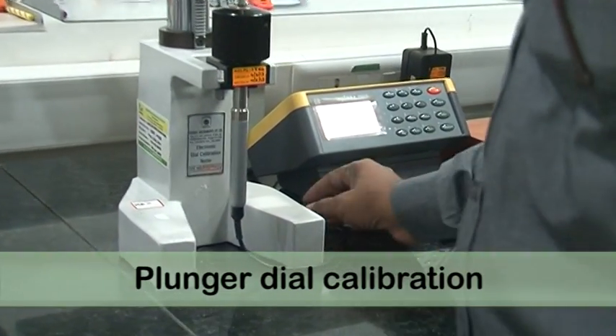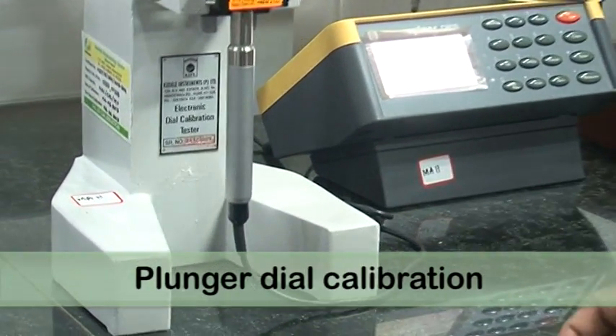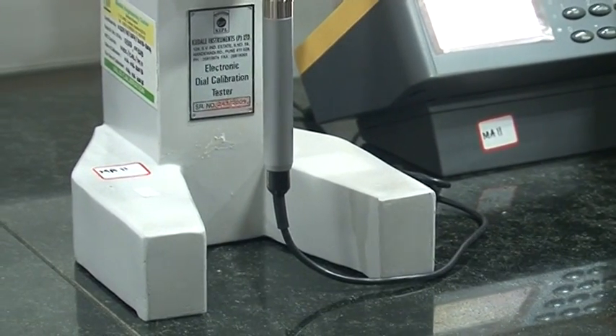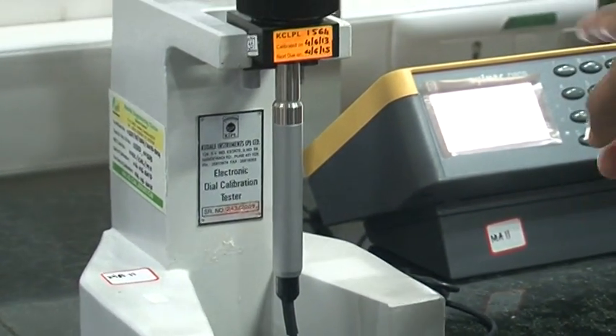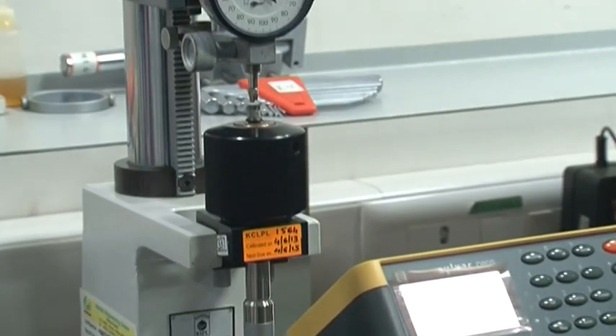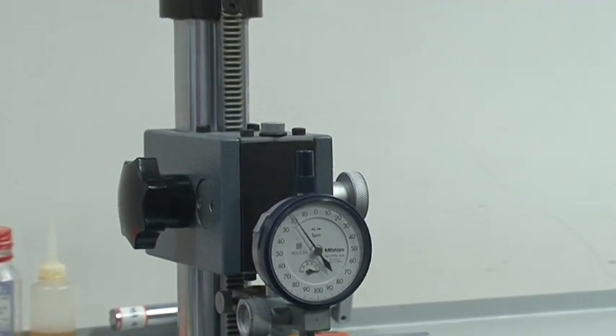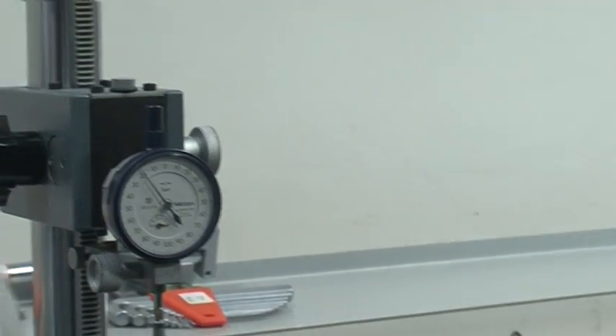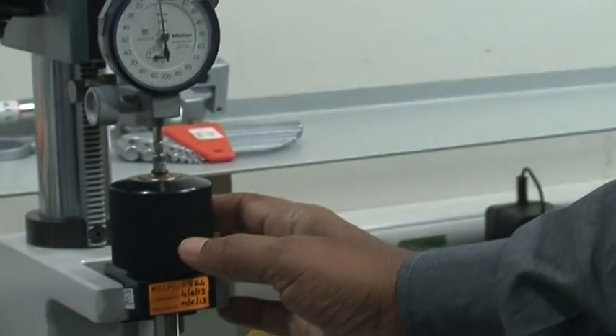Dial calibration. This instrument is used for calibrating plunger dials, lever dials and bore gauges. The least count of this instrument is 0.1 micron and the range is 25 mm. Now we are calibrating a plunger dial having a least count of 1 micron.